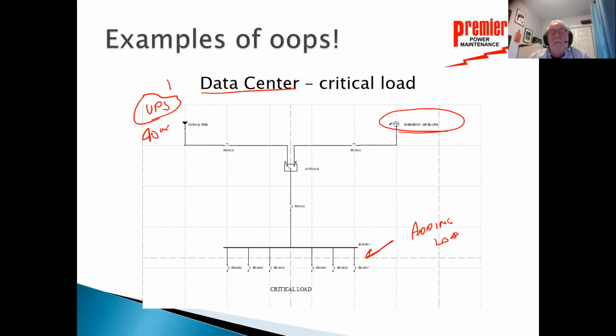Adding load. So the load kept adding here for the data center, but they never reviewed anything like that. And eventually the load got so large that this breaker feeding the data center tripped. They did not lose utility power. They did not lose the UPS. The emergency generator was still there, but they lost their system, and it was a long outage before we could get it back up. Again, a single point of failure.